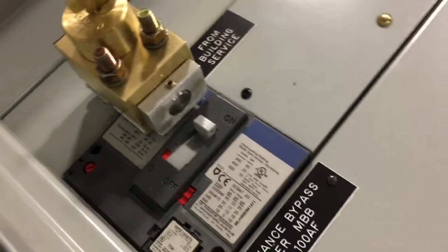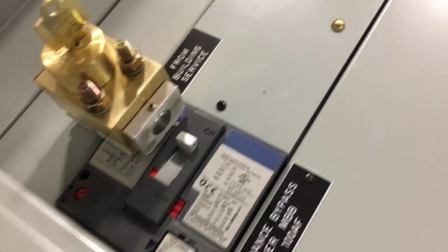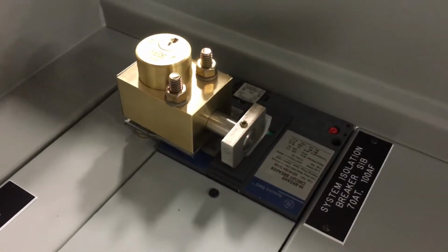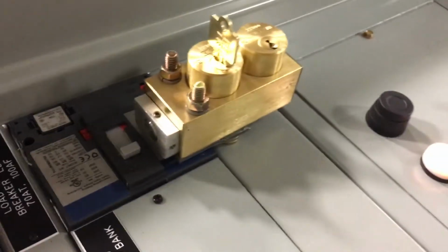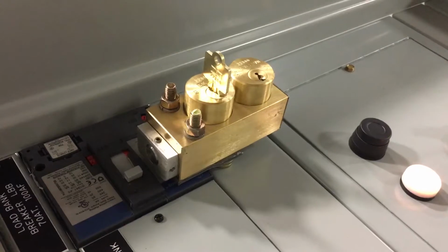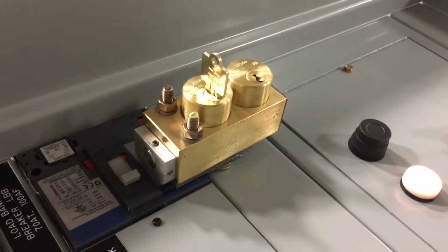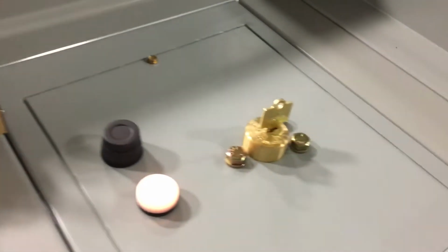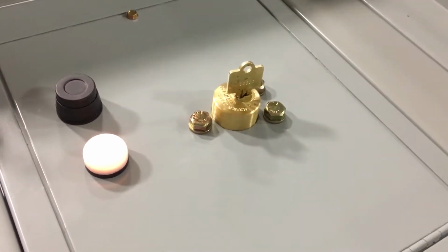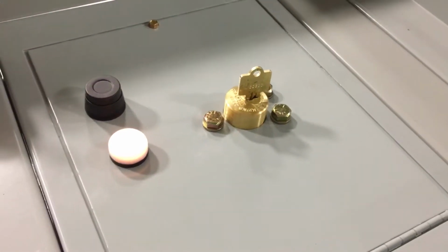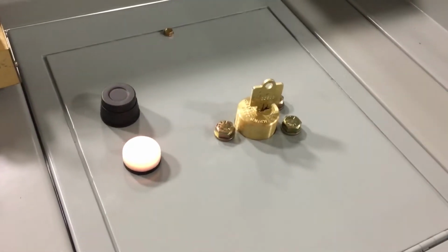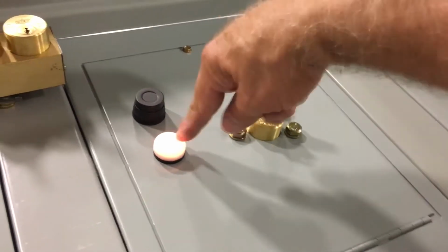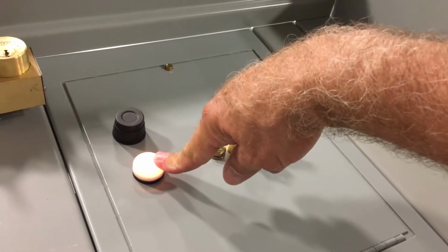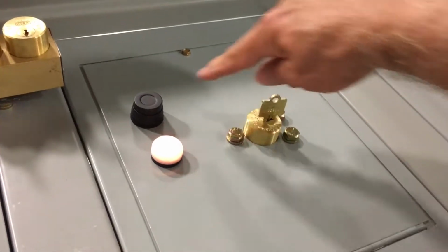So MBB is closed, SIB is locked open, load bank breaker is closed, so we're testing load bank, and key K3 is locked in the SKRU. To go back to normal mode, again the light has to be on, showing that the UPS system is in bypass mode.